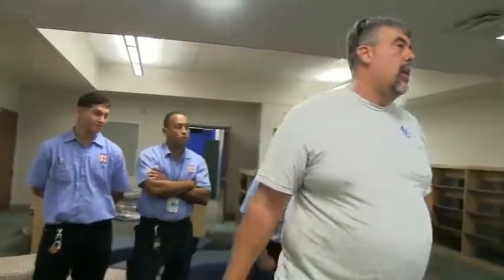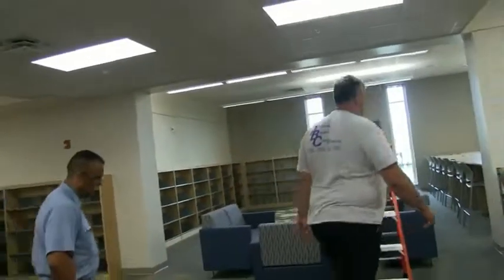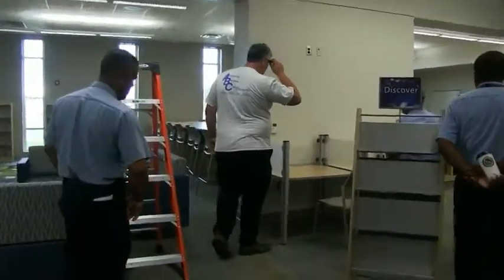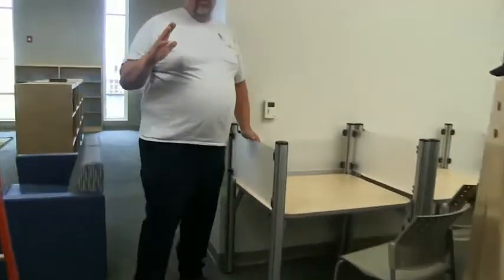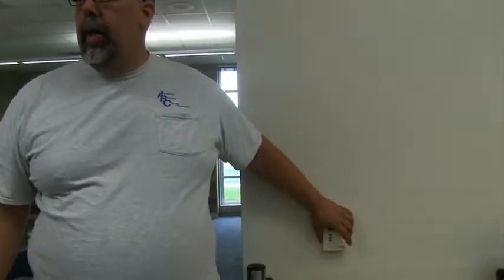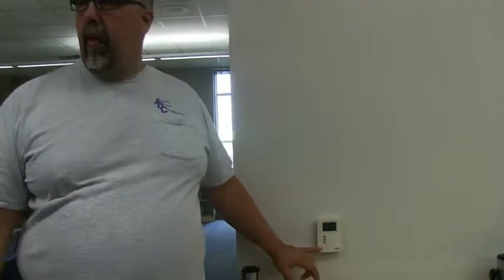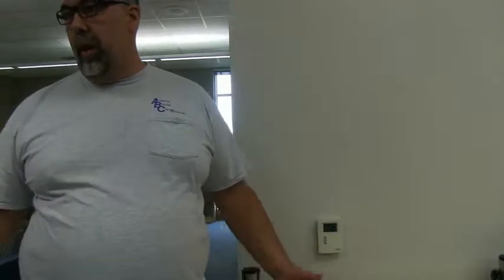Right there, inside the thermostat, there's the ability to override. The override lasts for 1 hour. After that, it sends an override to the air handler, and the air handler actually shuts its own override off. It doesn't look for this to go away. The air handler is only going to override for 1 hour, then it's going to wait for this to send another override back to it if it was necessary. But generally speaking, it shouldn't be, because once you're only looking to come down 2 degrees, that should happen within an hour.